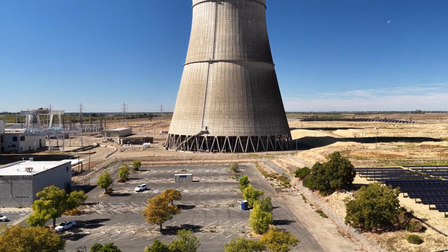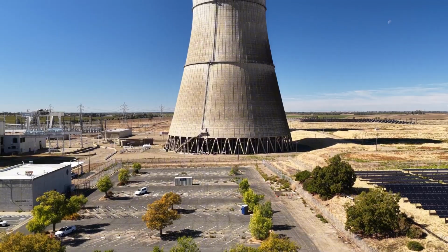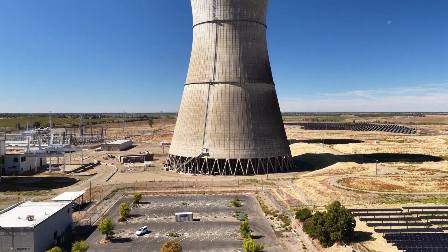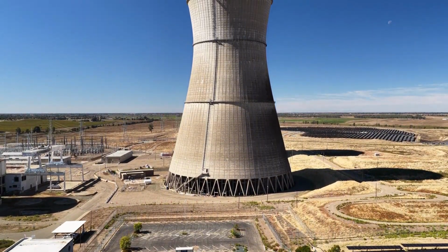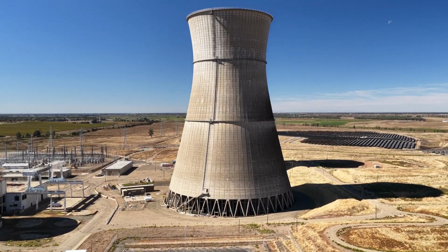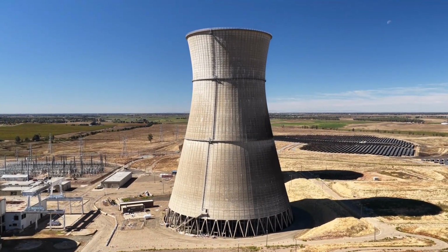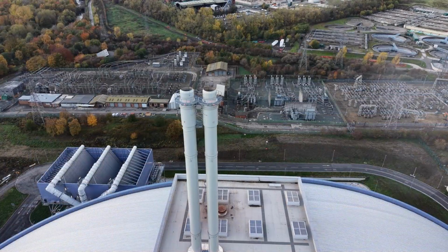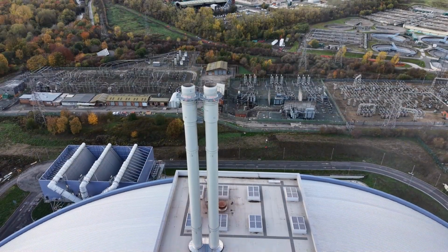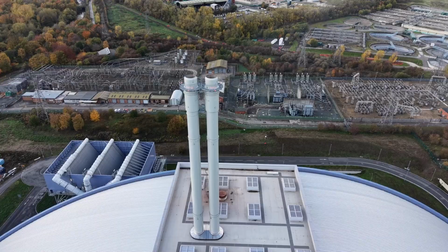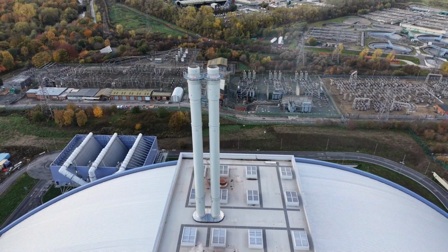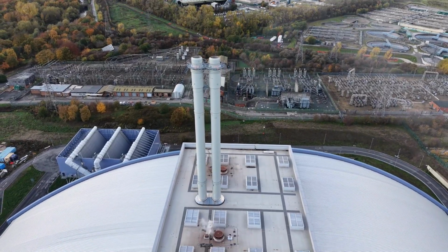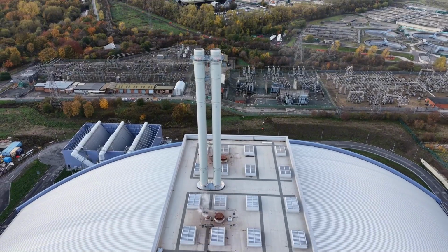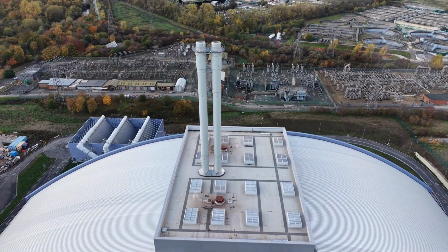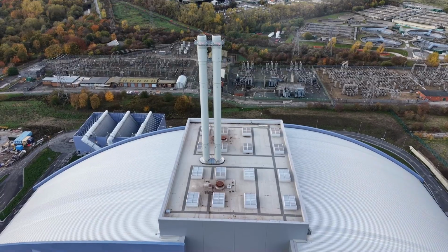For generator step-up transformers, the units that connect large power plants to the transmission system, the lead time averaged 144 weeks, nearly 3 years. In 2021, those same lead times were around 50 weeks. The change happened in 4 years. Between 2021 and 2025, lead times roughly tripled. The causes are layered.